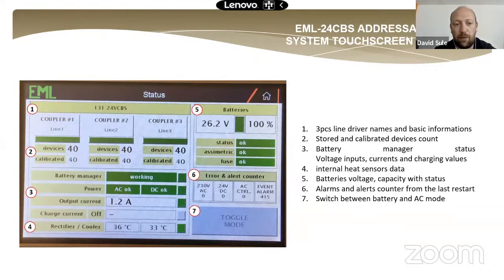So this system is with a maximum quantity of lights, 120 luminaires. All of the luminaires are calibrated. This calibrating means during the commissioning, the system can measure one by one the LED current of all of the addressable units. So it sends the calibrating message to the lights. All of the lights will turn on, and the lights will give back how many milliamps are going through the LEDs, and the panel will store this calibrated milliamp value one by one for every address.